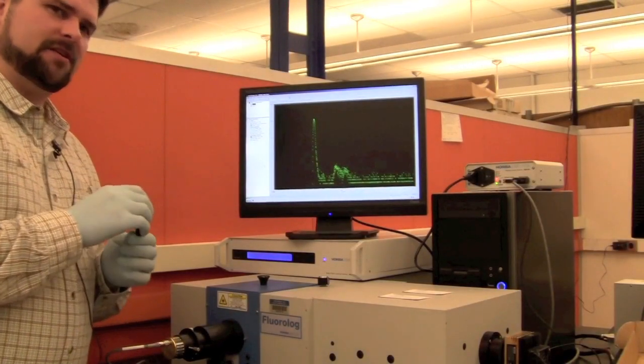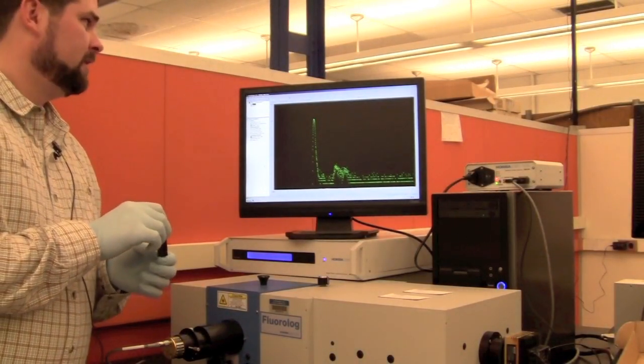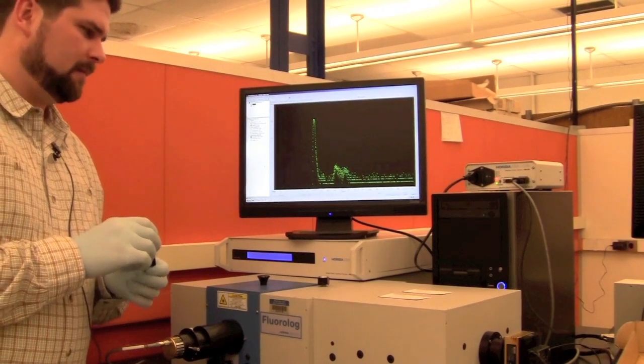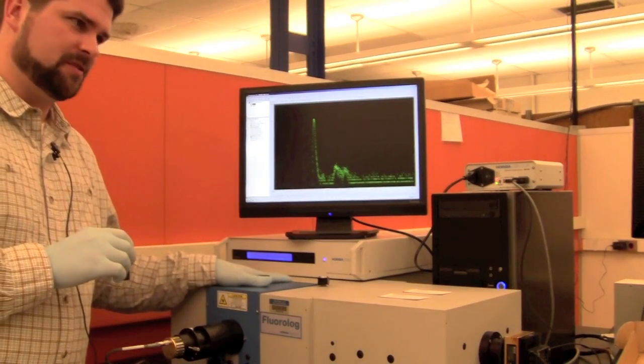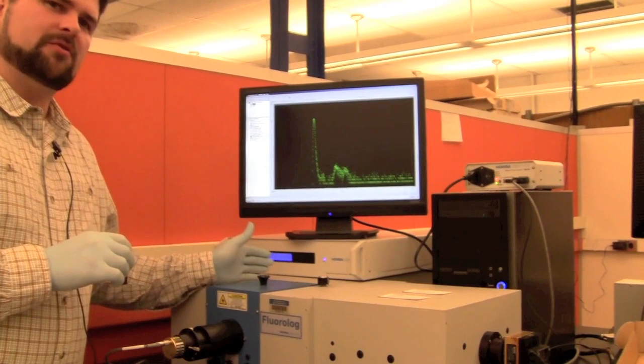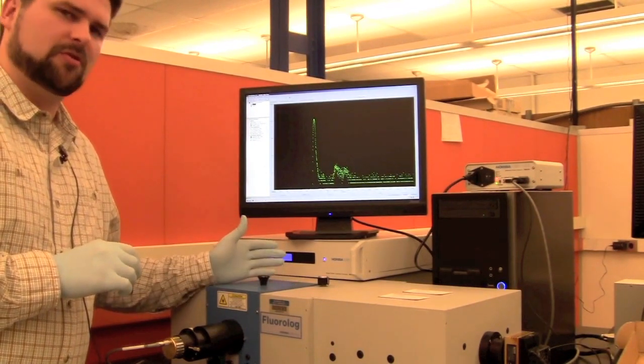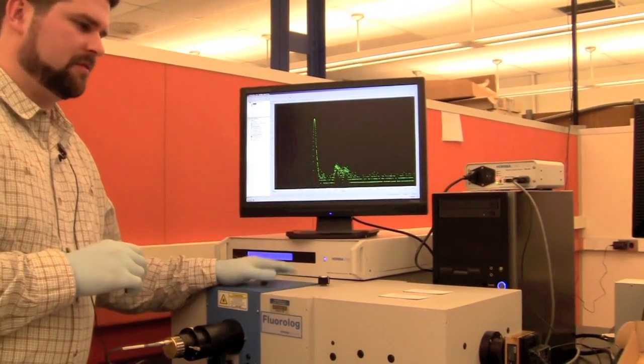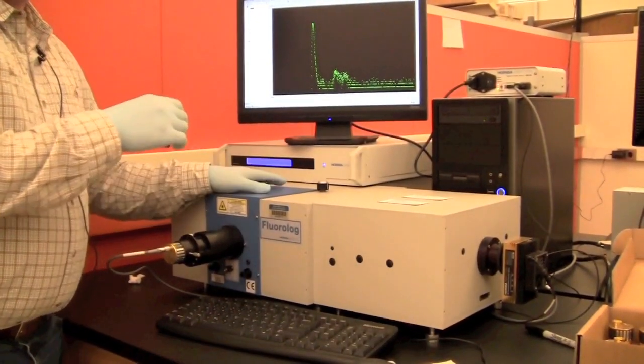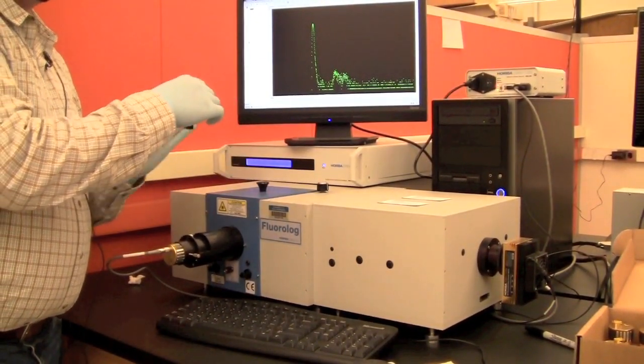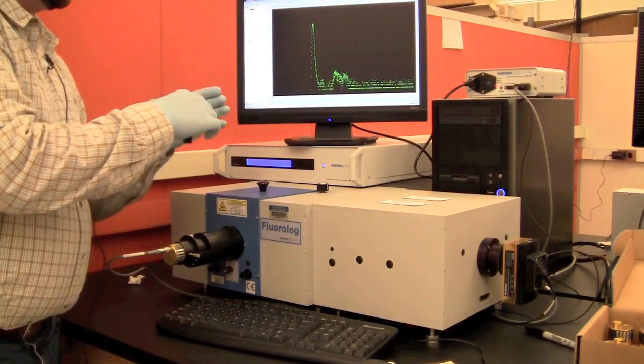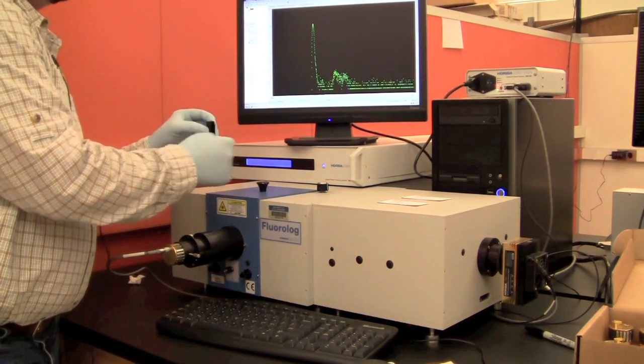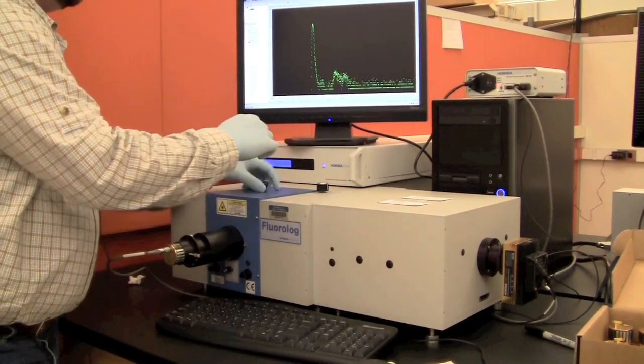I've placed in here 100 nanomolar duplex DNA labeled with Alexa 488 dye. Typical concentrations you'll use in this instrument are around the nanomolar range, the same concentrations you'd use in your normal fluorescence experiments. I'll place my sample in the same orientation with the two windows parallel to one another pointing this way and the one window pointing toward the detector.